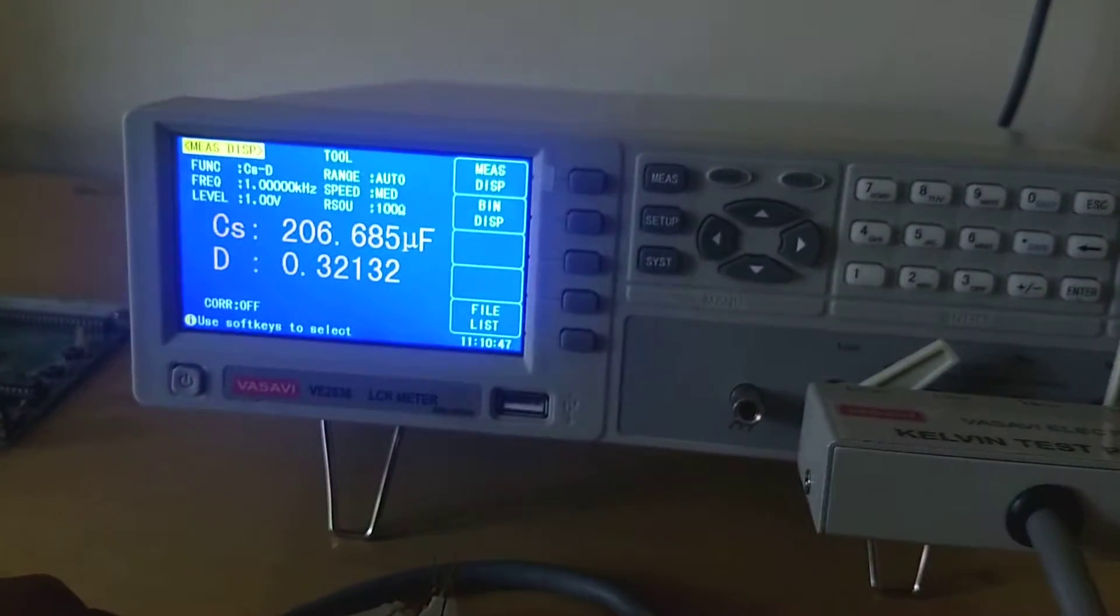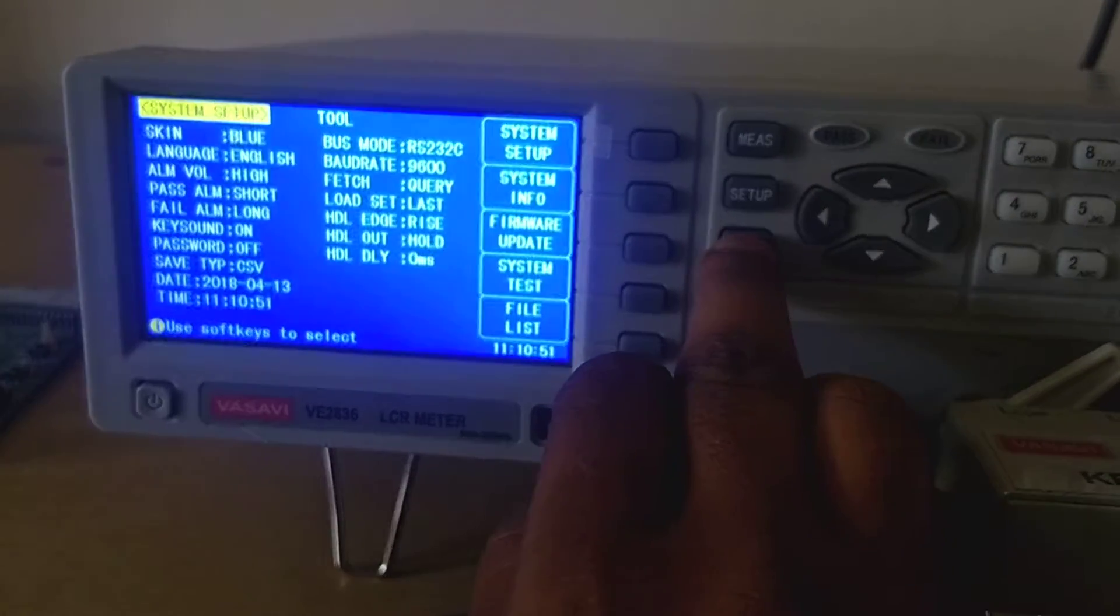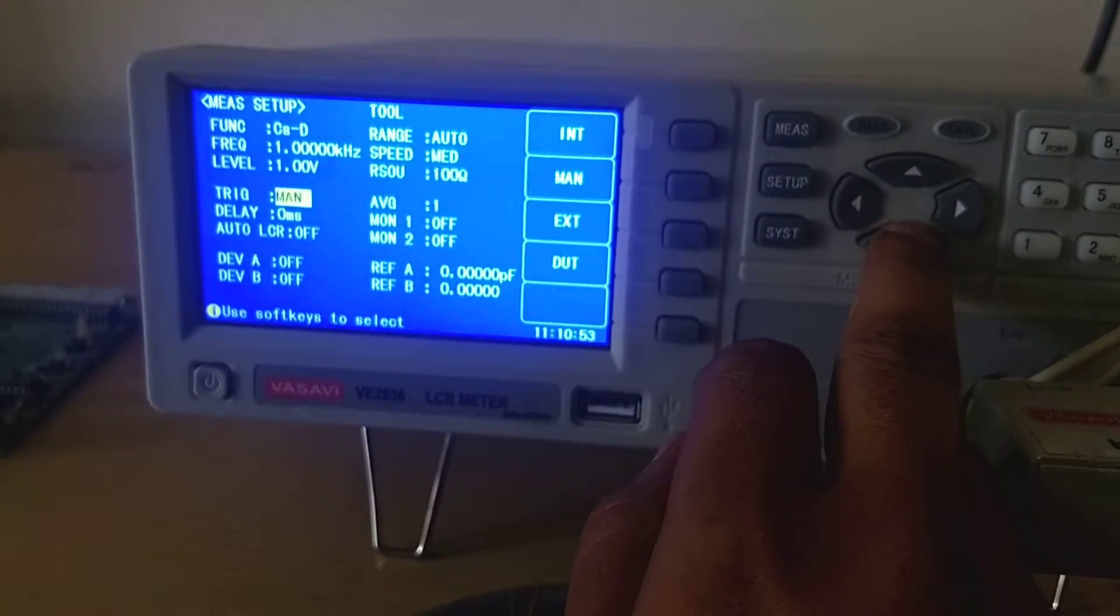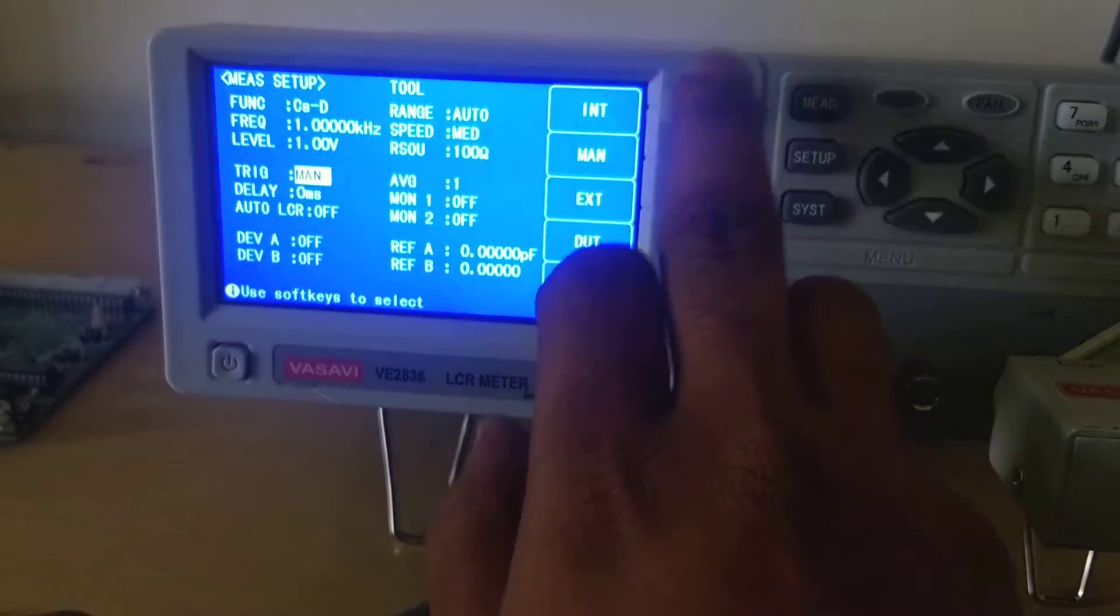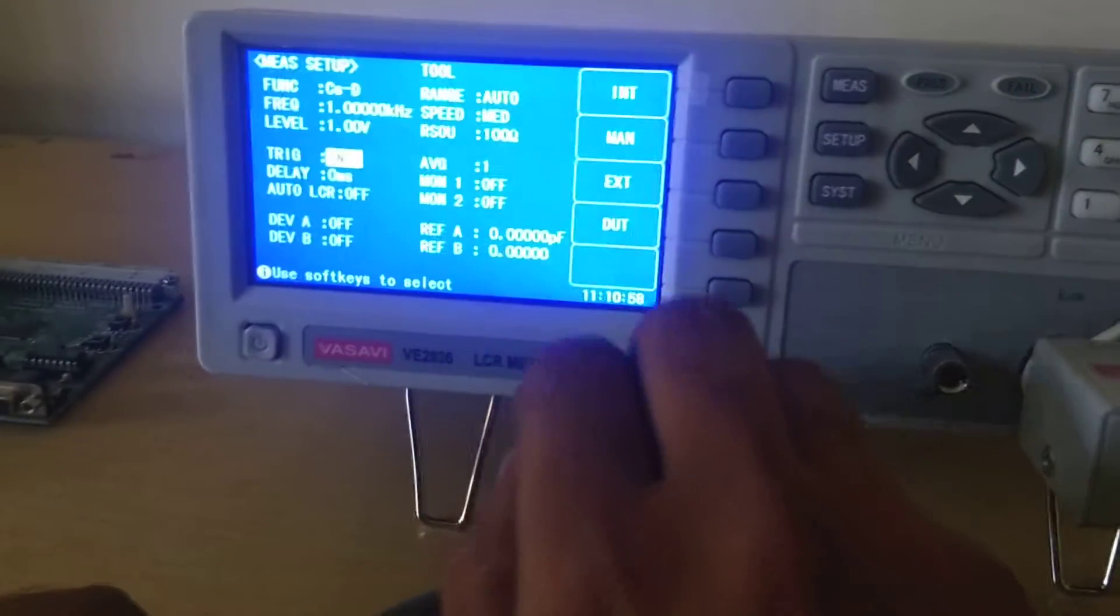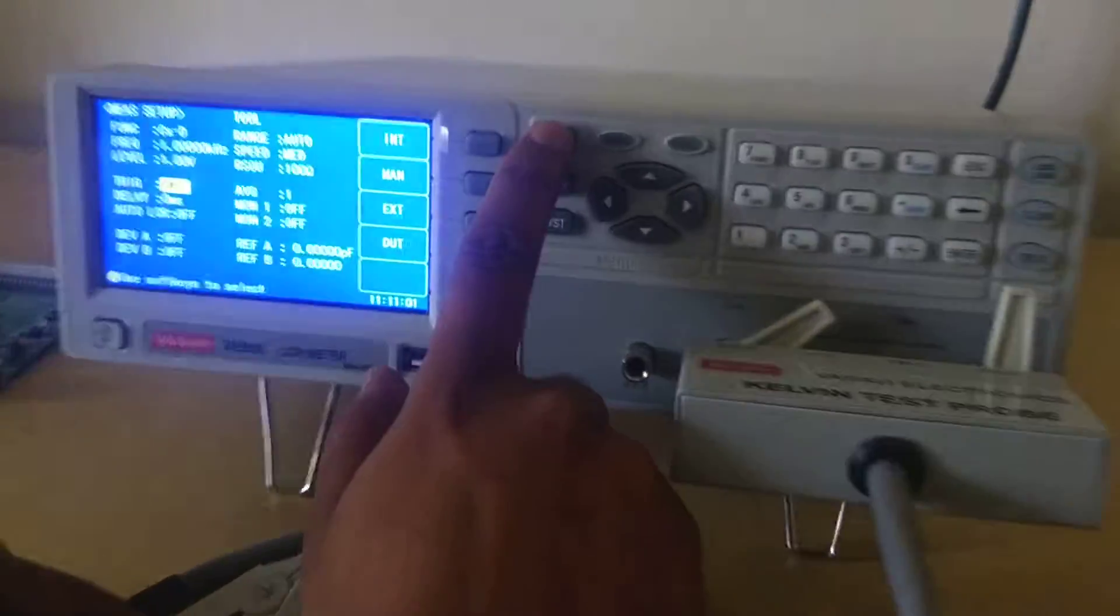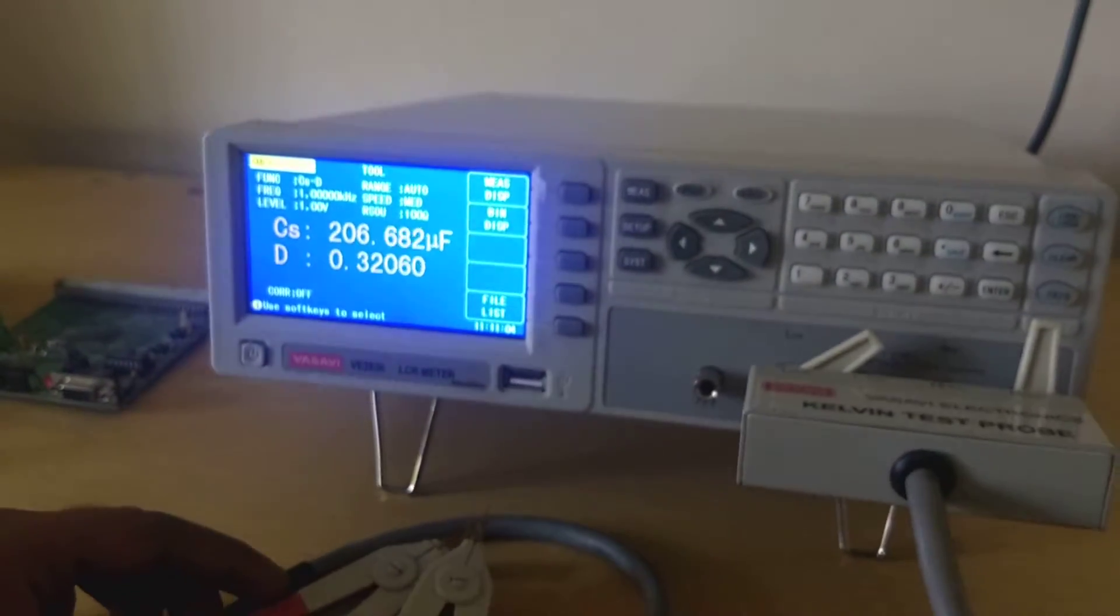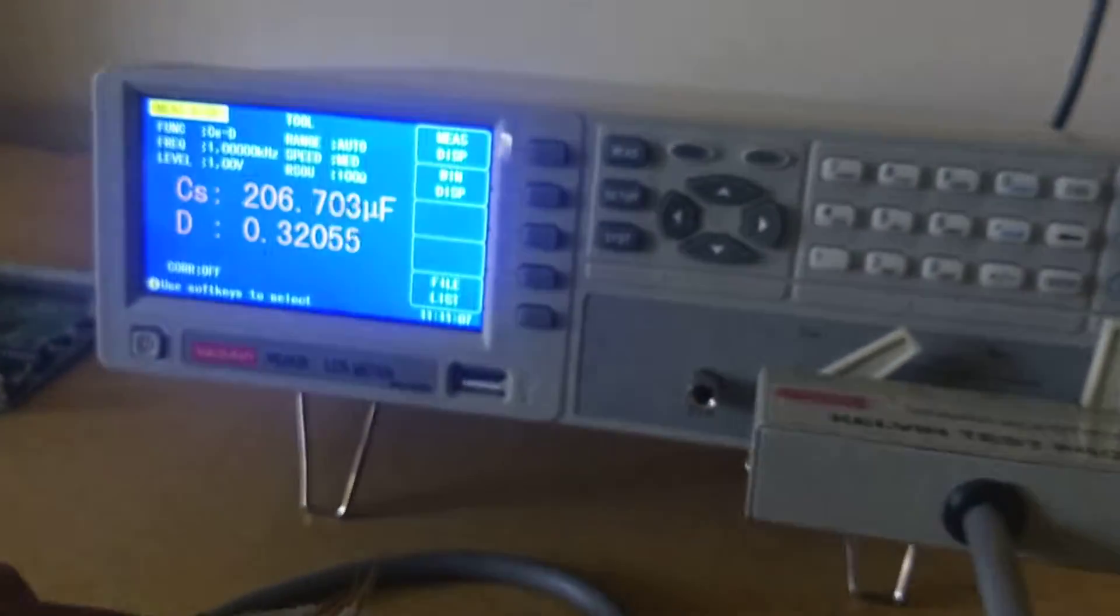Now I will show you how to change the trigger mode. In trigger mode, you need to select internal, manual, or external. You have to select internal trigger. See, now automatically it is in internal trigger. You need not press trigger in this mode.